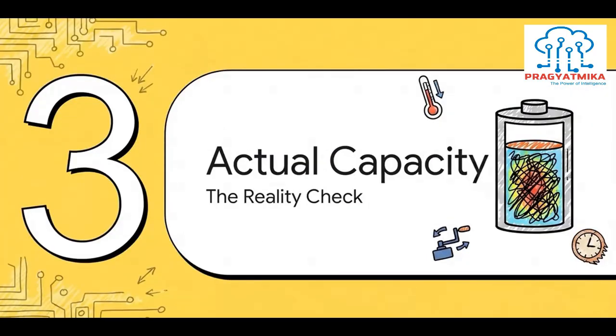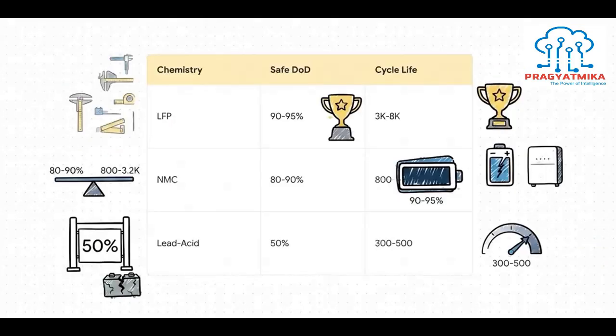Step 3, actual capacity, the reality check. This is where we have to adjust for the actual real-world physics of batteries. Because let's be honest, a battery's nameplate capacity is basically a lie. You absolutely have to adjust for depth of discharge limits and state of charge reserves, and those vary wildly depending on the chemistry.